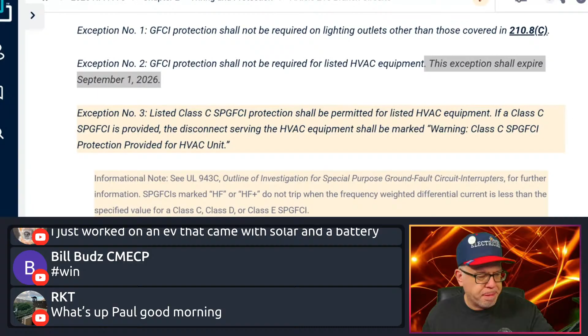Okay. Oh, and by the way, your Class A HF or HF plus clarifies that the SPGFCI classes C, D, and E are going to have some special purpose applications. There may not be the same milliamp thresholds as we would have for a normal Class A GFCI, but that's also why it requires the additional marking if you choose or elect to do that. We're not going to let somebody say, look, it just won't work, and I'm just going to circumvent the GFCI altogether. There are options now, supposedly, from the manufacturers. We'll hold them at their word, okay? So here you go. We are going to allow the Class A HF or HF Plus, or we're going to allow the Class C SP GFCI with additional marking requirements. Okay, it's going to be allowed.